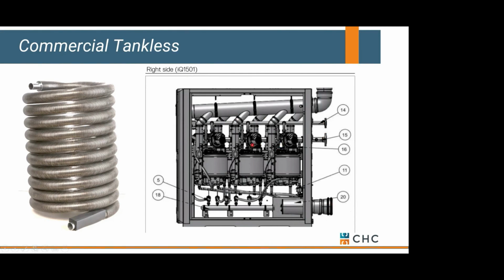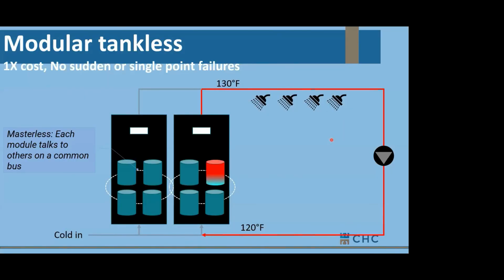The thing that's really important about IntelliHot or tankless in this aspect is the fact that each one of these engines has its own motorized isolation valve and also has its own flow meter. And what's cool about that is if you know the flow in your system and you know the delta T, you can do something we call BTU staging, which means you know exactly how many engines and burners need to fire in order to recover the hot water required out in our system. Okay, so it's a very smart, very intelligent water heater design.